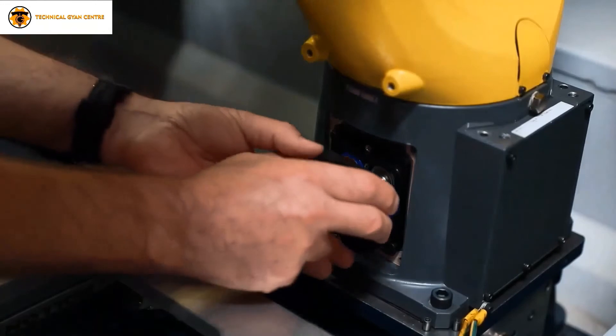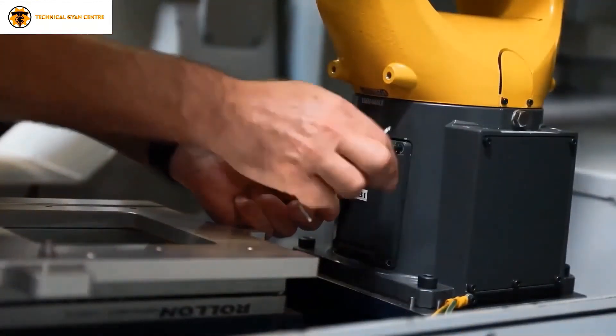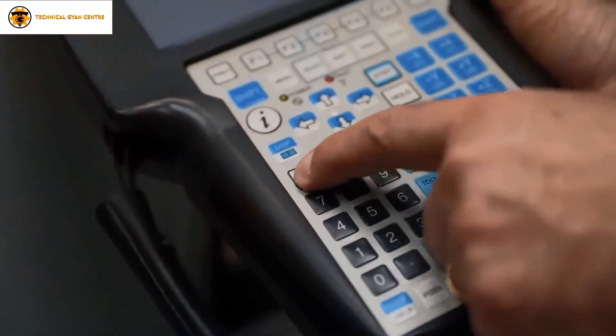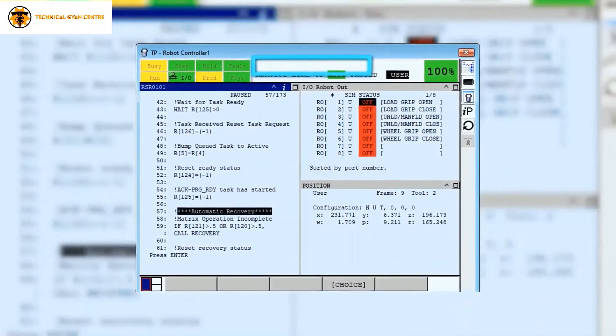After installing new batteries, put back the battery cover properly. Now press the reset button on the teach pendant. The BLAL alarm should get reset. If the alarm is not getting reset, please check the polarities of the batteries again.